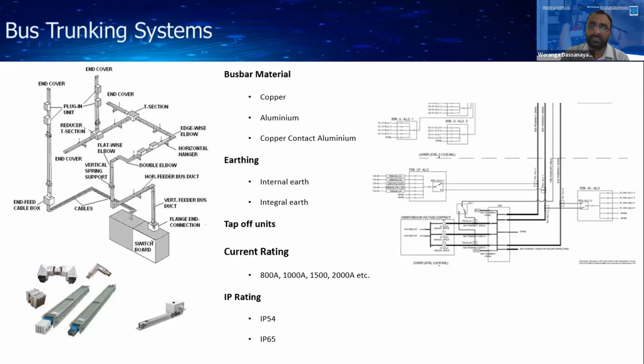Because in most circuit breakers the contacts are tin-plated copper, if you directly terminate an aluminium conductor to a circuit breaker, a bimetallic reaction can happen at the contact point. If that continues for a long time, the contact is not adequate to pass the current to the system. Therefore, the termination point can be heated because of this corrosion, and after a long time, because of the heat, a fire hazard can also happen.